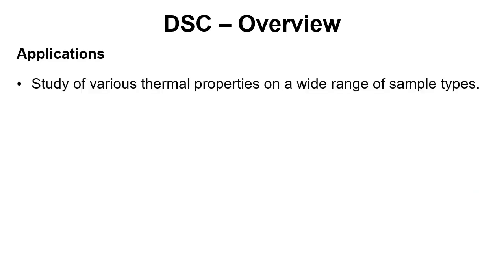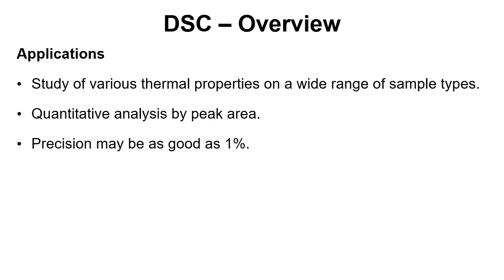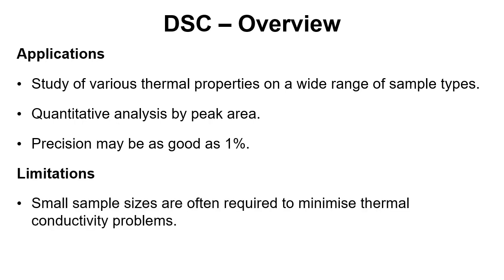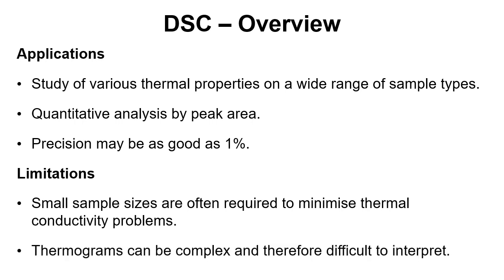In terms of applications, we can study various thermal processes for a wide range of materials, and it allows quantitative analysis because we can look at the peak area, which is proportional to the energy associated with the thermal event. Precision can be as good as one percent. Limitations include the requirement for small sample sizes, just as with DTA, to minimize thermal conductivity problems. We also need good thermal contact between the sample material and the base of the pan to ensure good heat flux and heat flow. Additionally, thermograms can be quite complicated and difficult to interpret.